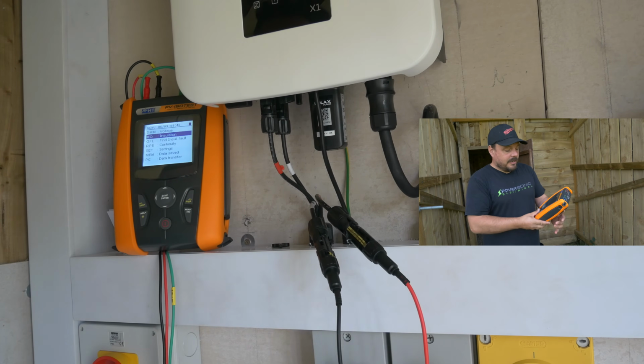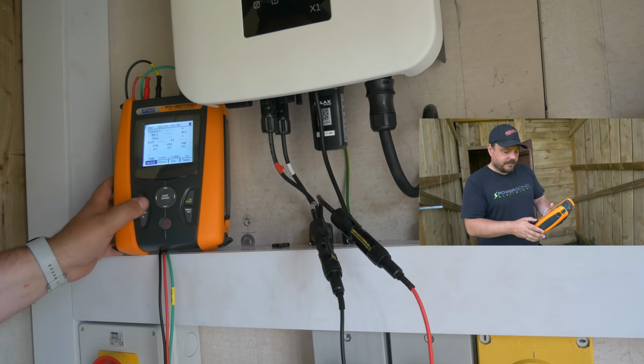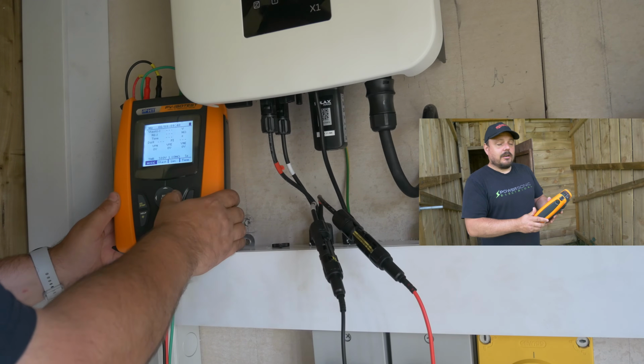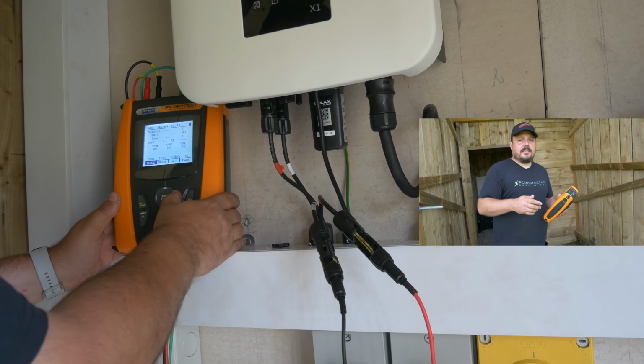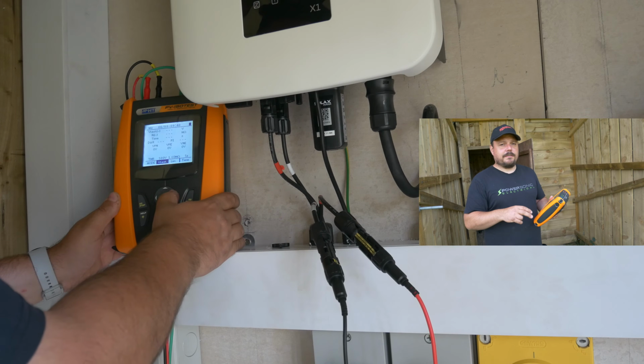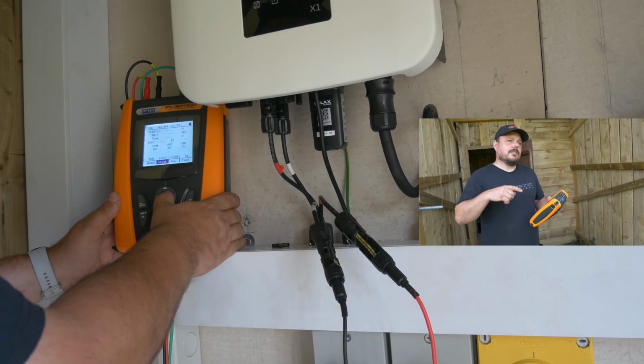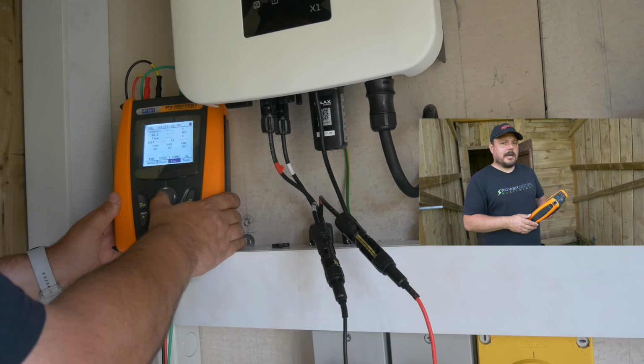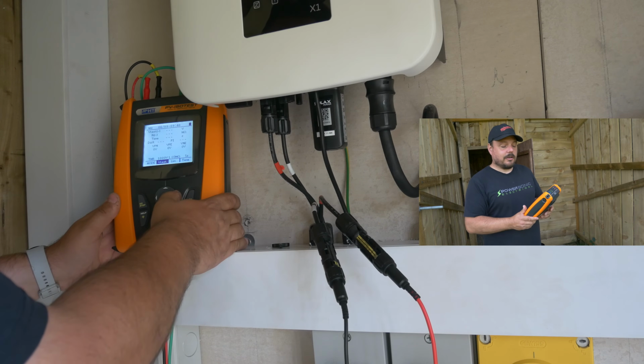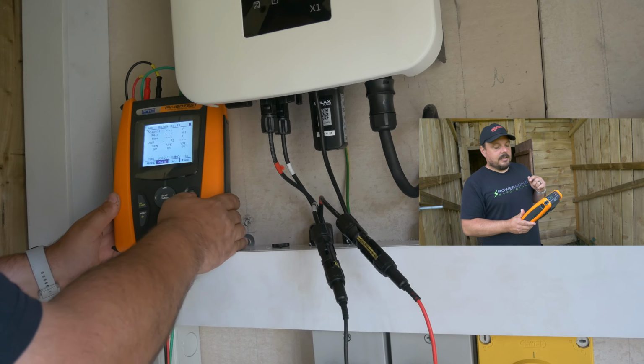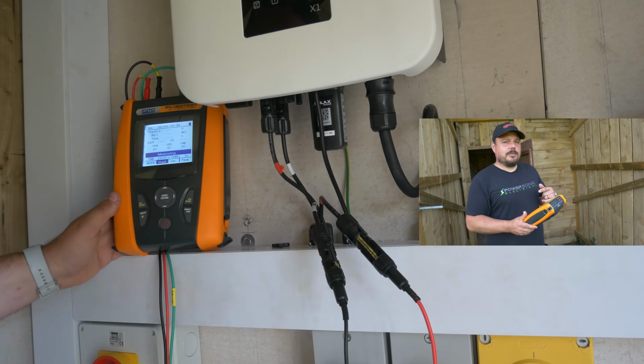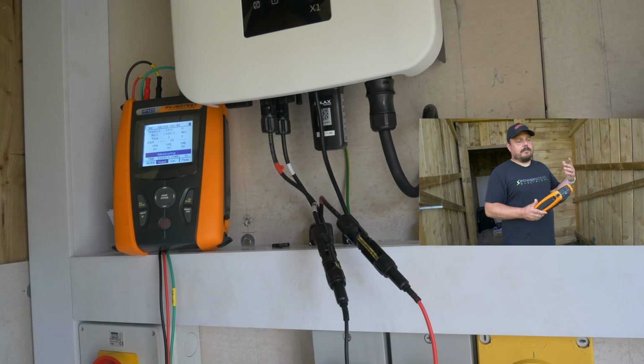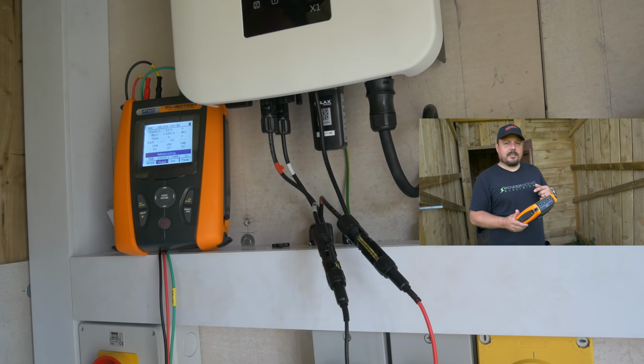behind me. But in essence, this has a few different test features. You can do your insulation resistance testing. Now with this one, it will do it up to 1500 volts on the strings. So if you've got a big array that's generating a lot of power, this will happily still carry out your insulation resistance test. It can also do an earth continuity measurement. So if you've got an array frame that's earthed, it can check to make sure you've got the continuity in place between there back to the main earthing terminal.